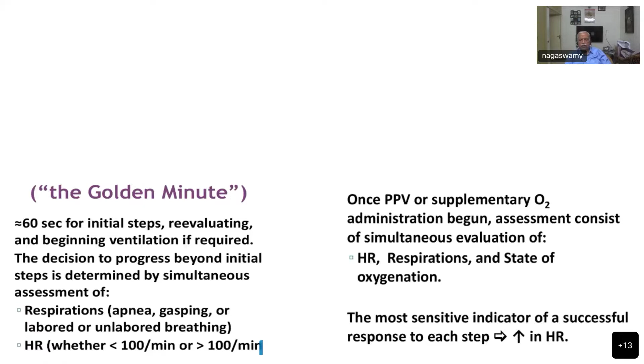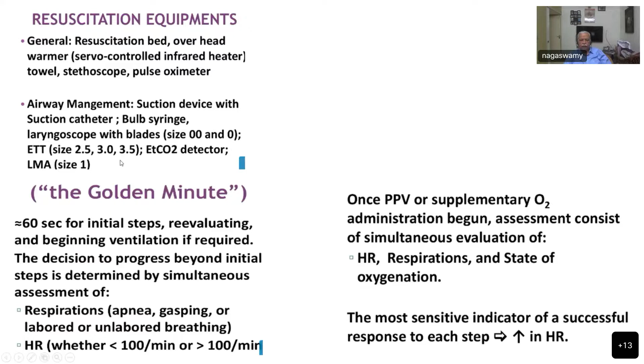And resuscitation equipment, what you need are the resuscitation bed or overhead warmer, towel, stethoscope, pulse oximeter, and airway management suction device, suction catheter, bulb syringe, laryngoscope. You must have the lowest, smallest size blades, 0 and 00, and ET tube, 2.5, 3, 3.5. ETCO2 detector, and nowadays they recommend LMA. LMA was introduced as an alternate airway equipment only in 2015. In 2010 it was not there. So such small changes have been done.